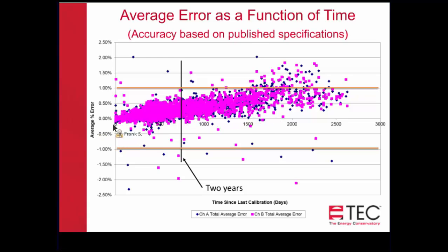So they will track, instead of a negative accuracy, a positive accuracy, you can see them all moving in an upward direction. So the vertical line shows the 2-year period, and you can see the yellow lines represent the 1% of accuracy. So when we get to 2 years, we start to see more and more data points starting to exceed the 1%. Certainly when we get out to 3 years, it gets to be more. 4 and 5 years tends to be very much scattered and definitely outside of our calibration range. So we want to be on the safe side with making sure that everyone's instrument is sufficient and accurate for all of the tests that they're performing. So that's why we've limited it to 2 years.